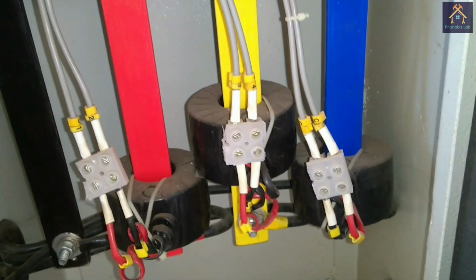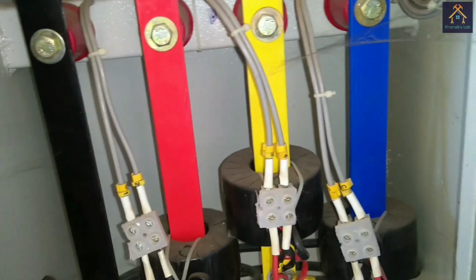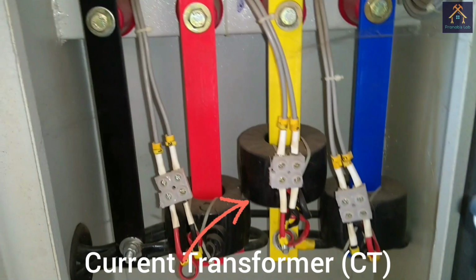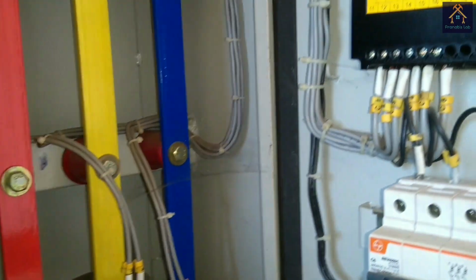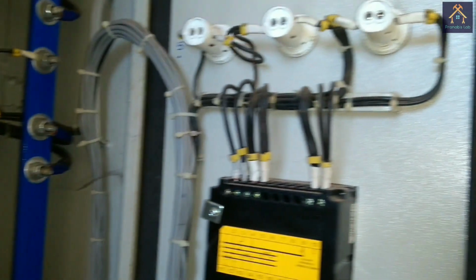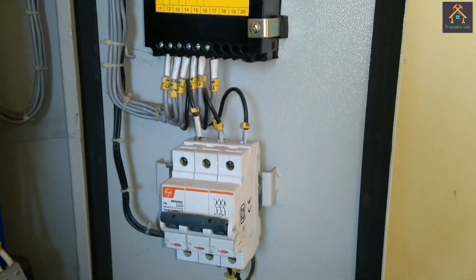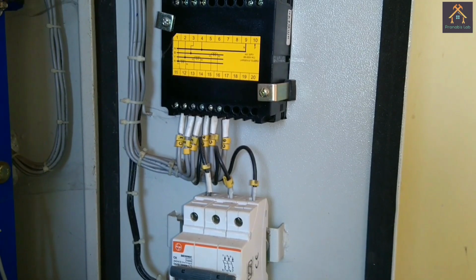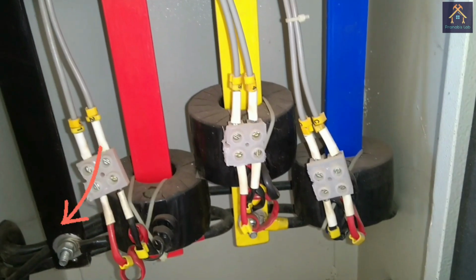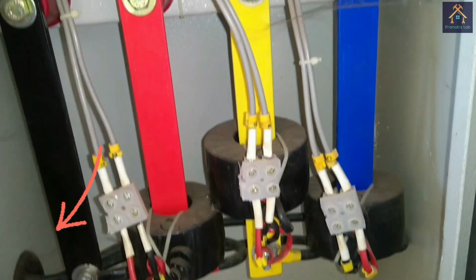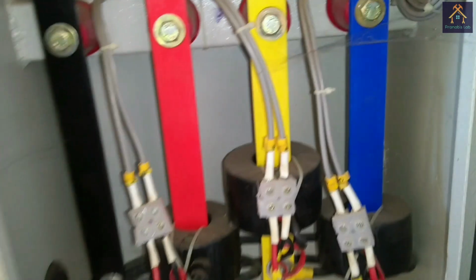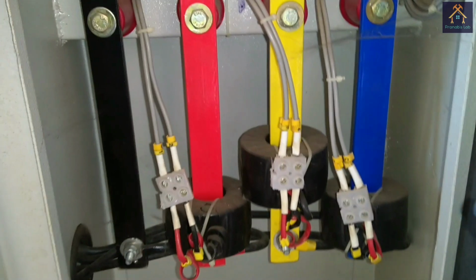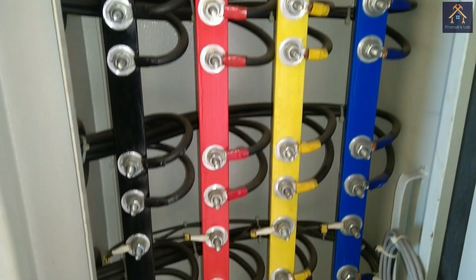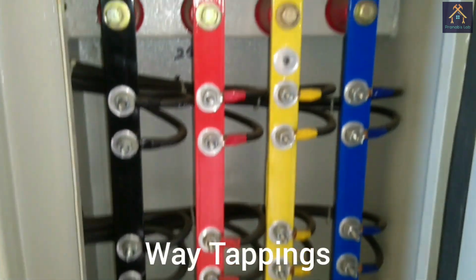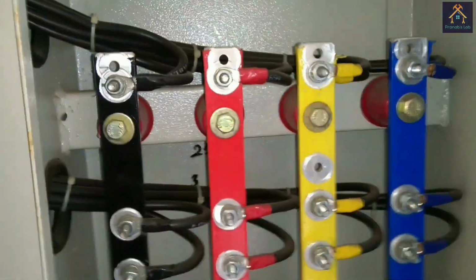Now here you can see the 3 different cylinder-like structures inserted into the bars. That's the current transformer or CT. The secondary of the CT is connected with the multifunction meter and helps to measure the current drawn by each bus. Please look at the neutral bus. There is no CT inserted inside the neutral bus because the current flowing through the neutral is always zero in a balanced three-phase network. So you can see the different tappings are taken from the bus bar and inserted into the next chamber.